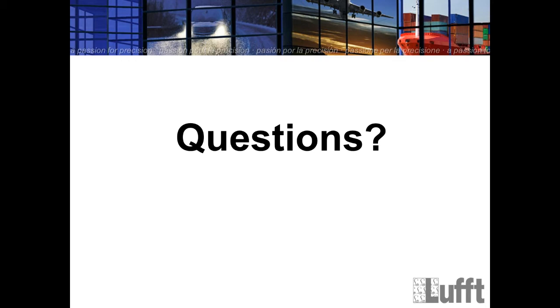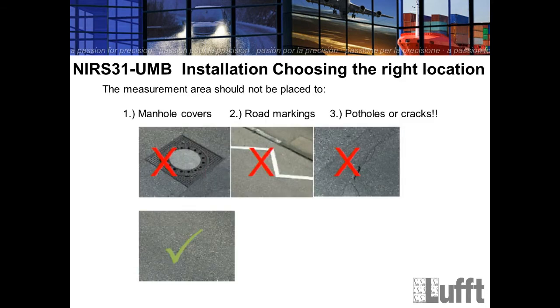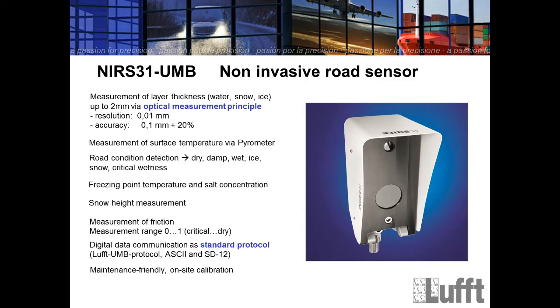NIRS measures salt concentration. How does NIRS measure salt concentration? Maybe we can go back to this sheet. The freezing point and the salt concentration are calculated. Again, we have a link between freezing point temperature and salt concentration. They are linked together. So if you use the formula, there is a special formula to calculate the freezing point and the salt concentration using this ice percentage level.